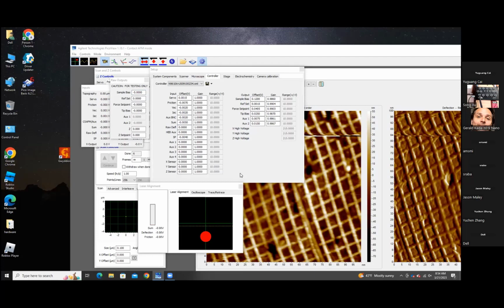Don't worry about the electronics. This is what is important. If you have the head electronics box that has the 4.3 gain in the circuit, you'll see a deviation of 4.3 between that deflection value and the sample bias value you put in. So for the individual that had that issue earlier in the conversation, that's one way you can check it. Change your sample bias to 1 volt, and if your deflection goes to 4.3 volts, that's the version of head electronics box you have in your system.